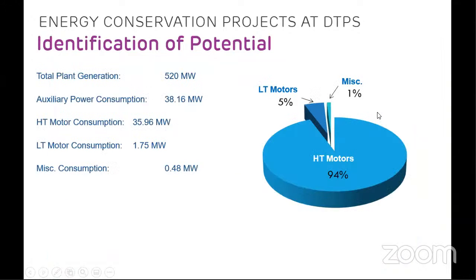So for identifying which applications we can install VFD in our plant, we carried out a survey. Total plant generation was 520 megawatt and the auxiliary power consumption for running this plant was 38 megawatt, which is roughly 8 to 10% of the plant generation. High voltage motor consumption was 35 megawatt and low voltage motor consumption was 1.75 megawatt. Miscellaneous consumption, which includes lighting, air conditioning, and other consumption, was only 0.5 megawatt. So here you can see miscellaneous consumption is 1%, LT motors is 5%, and HT or high voltage motor consumption is 94%. It may vary with every plant, but this is just what we found out in our plant.